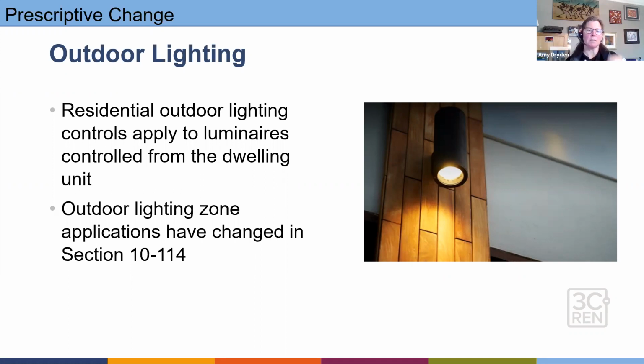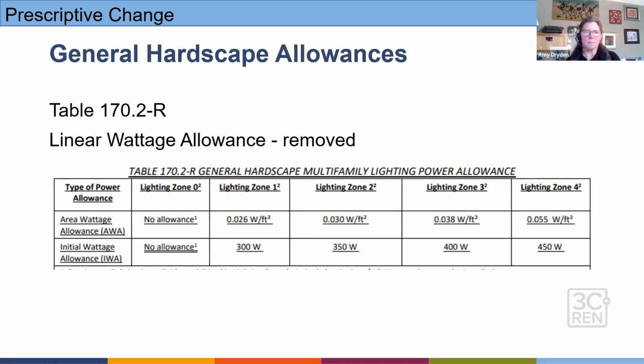The outdoor lighting zone applications have changed a bit, really. There used to be 3 zones, and now we have an additional zone where urban has been broken out into 2 zones. So that's a recent change. The next slide. Under general hardscapes, there's been a change here. You'll notice that we just have area wattage allowance and initial wattage allowance. We don't have the linear wattage allowance, right? Which is that contribution as you're totaling up the perimeter of that hardscape and determining what is allowable under the code. So now we're just looking at area and initial wattages for the general hardscapes. So a slight change in that methodology.